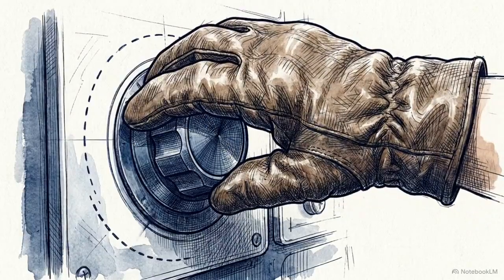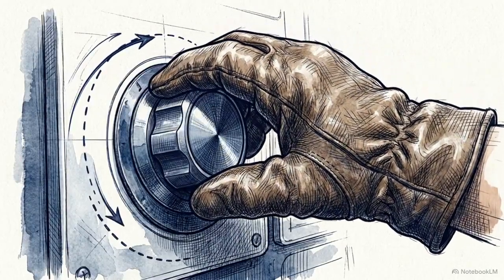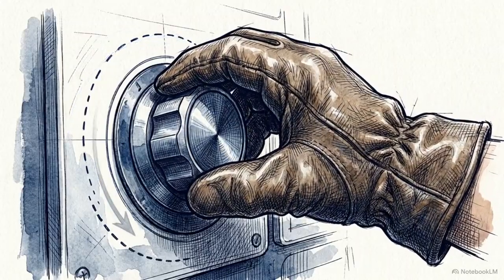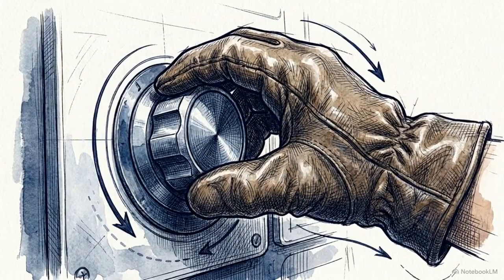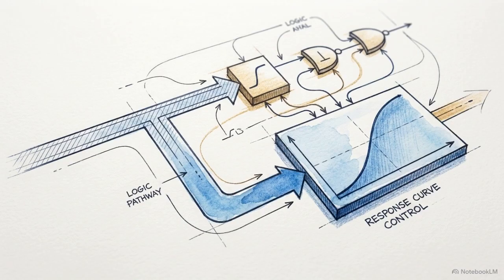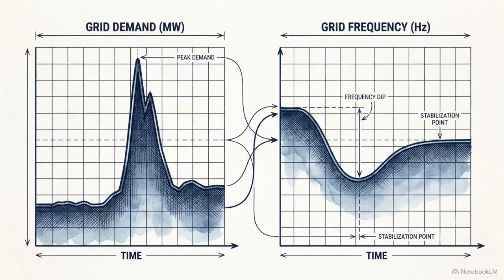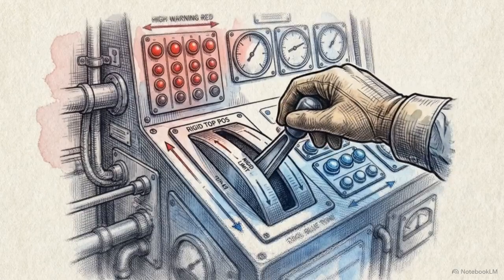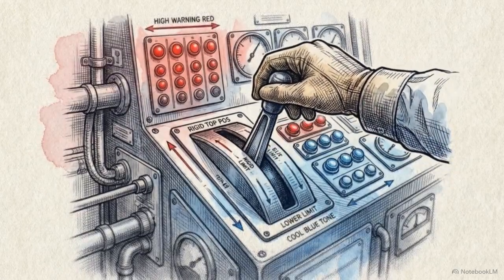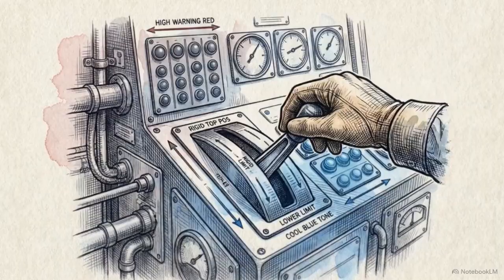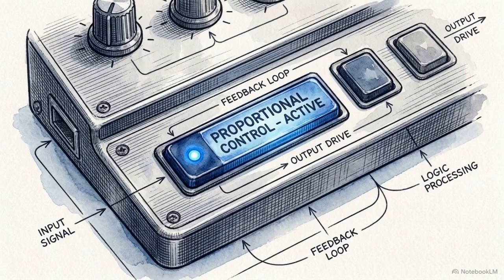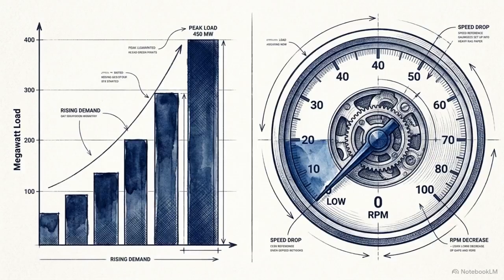To enable passive cooperation between these massive machines, engineers must introduce an intentional, calculated degradation of the speed reference. They have to abandon the goal of perfect zero-error frequency and implement a proportional response parameter. True system stability on a parallel grid requires an engineered give. Rigid perfection must be traded for mechanical flexibility in order to keep the massive machines from tearing the system apart. This control algorithm is called Droop mode. In Droop, the internal speed reference is allowed to decrease in direct proportion to the active megawatt load applied to the generator.